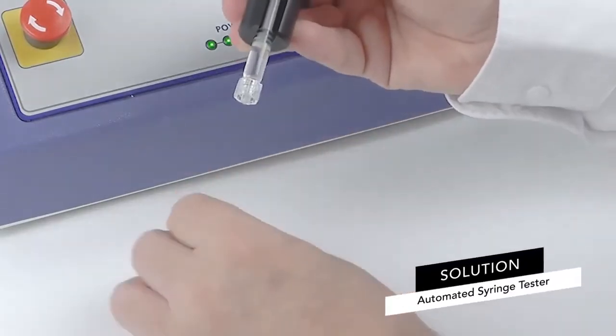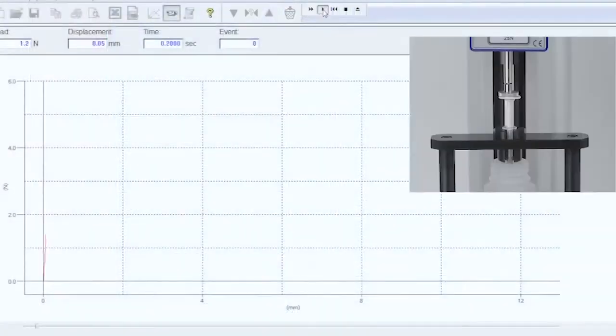Mecmesin offers a standalone test system for checking the break-loose and glide force of an individual syringe. Operators manually load each syringe into the tester, start the test and then unload the syringe when finished.